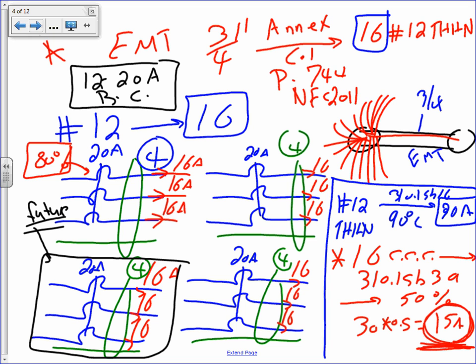So here's what I would do. Personally, instead of pulling these 4, I would pull 3 of them, and I leave this one for what? Future. That's a good design. So instead of putting all these 4 in one conduit, I put 3 of them in one conduit. So 3 times 4 gives me 12 conductors. So I'll have 12 conductors.